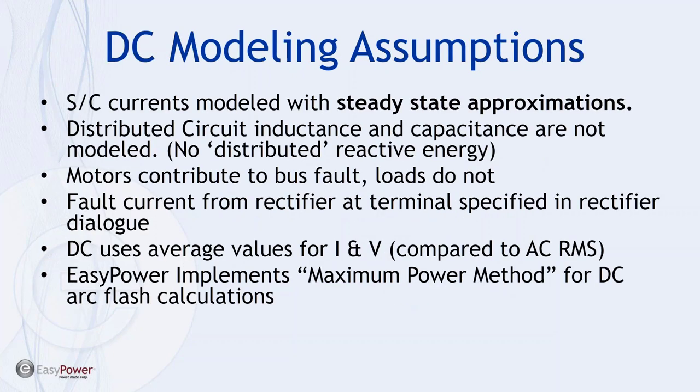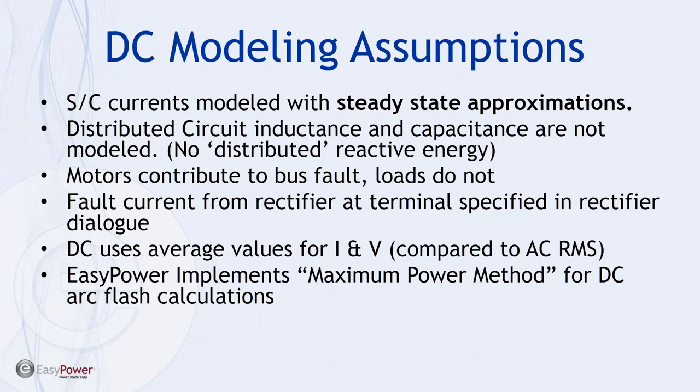To start with the assumptions that we want to make in DC. It's worthy of note that EasyPower in the EasyPower arc flash suite you can model AC systems, DC systems and hybrid systems all at the same time which gives you ability to see the interaction interdependence especially in your hybrid system. Short circuit currents are modeled with steady state approximate value in DC. Distributed circuit inductance and capacitance are not modeled. The motors contribute to a bus fault. Loads do not. Fault current from rectifiers at the terminal specified in the rectifier dialog. The DC uses an average value for voltage and current as compared to the AC RMS value. And then EasyPower implements the maximum power method as described in NFPA 70E.